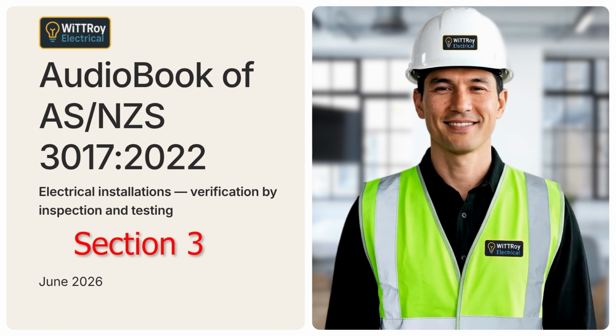Fault protection should also be checked. Fault protection means protection against indirect contact with exposed conductive parts if a fault occurs. Examples include automatic disconnection of supply, double insulation, or an isolating transformer. In simple terms, if a fault makes a metal part live, the installation must have a method to protect people. Protection against hazardous parts should also be checked. This includes protection by enclosures, guarding, or screening. It may involve parts that are hot, parts that could cause physical injury, or areas where flammable material could be affected. Protection against spread of fire should also be checked. For example, where wiring passes through a fire barrier, the fire protection must not be weakened.